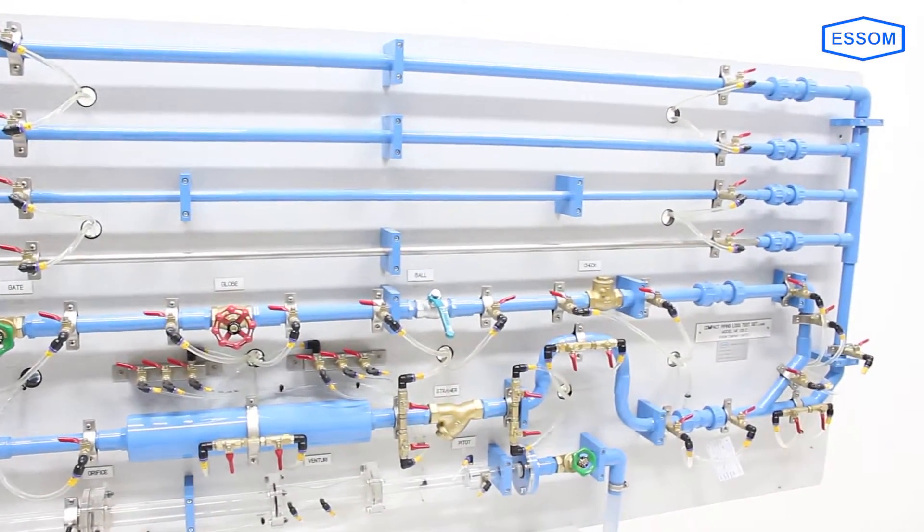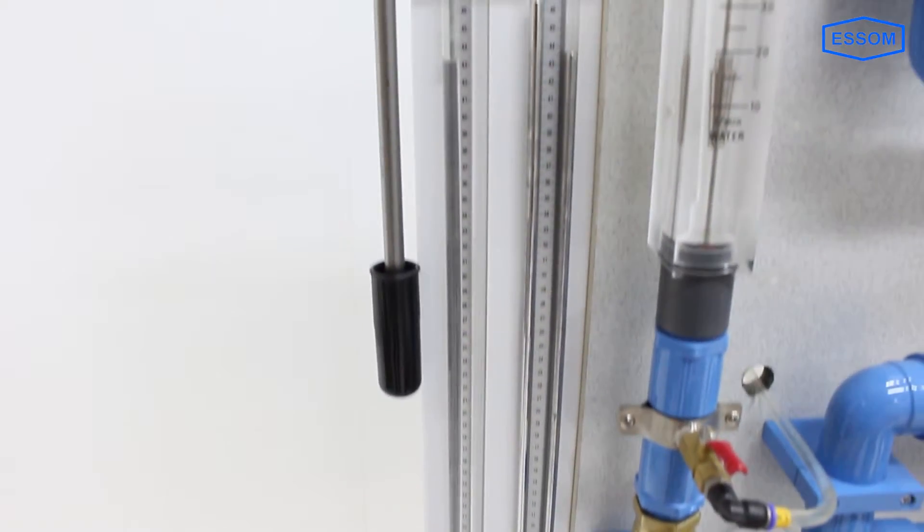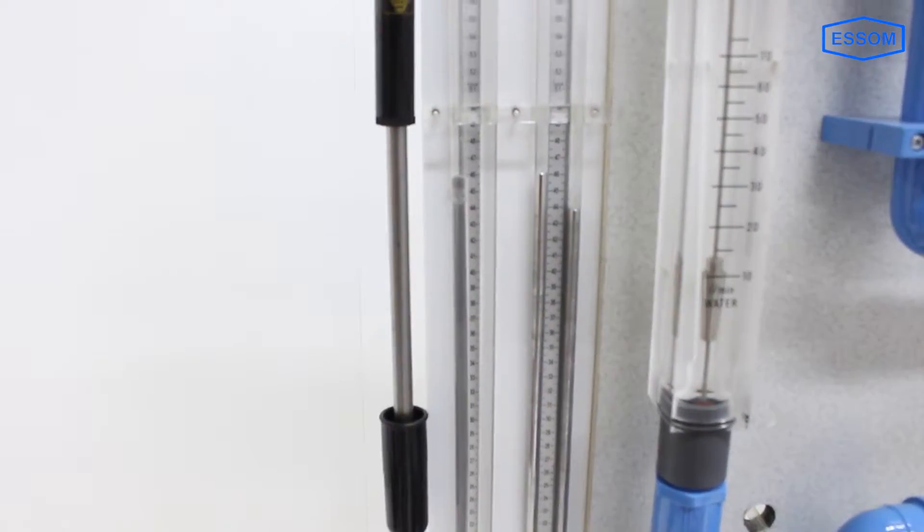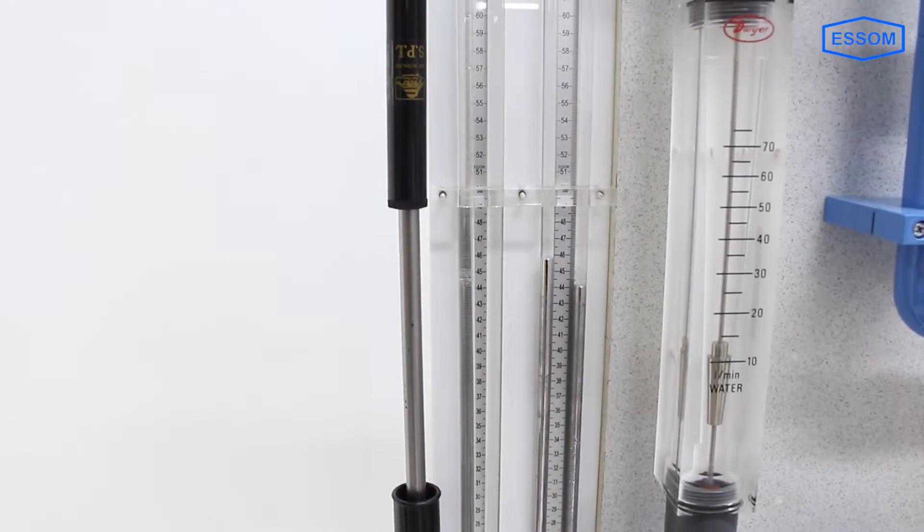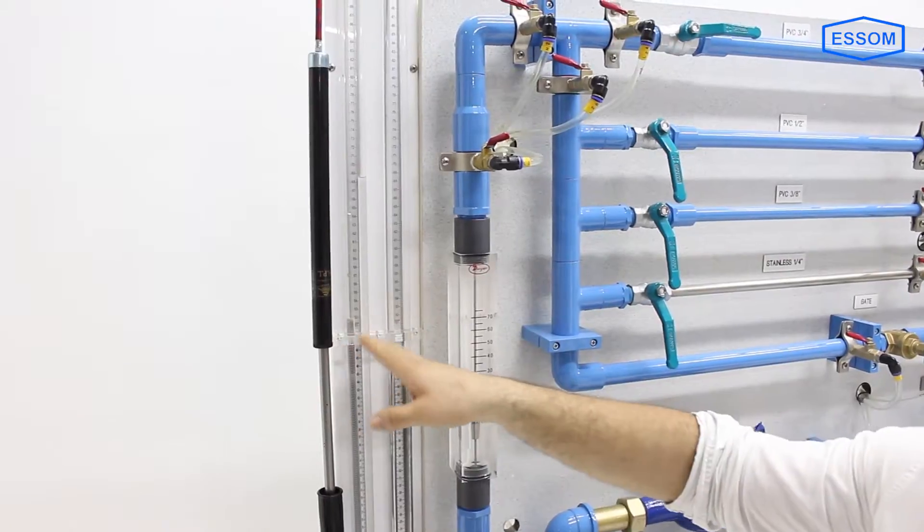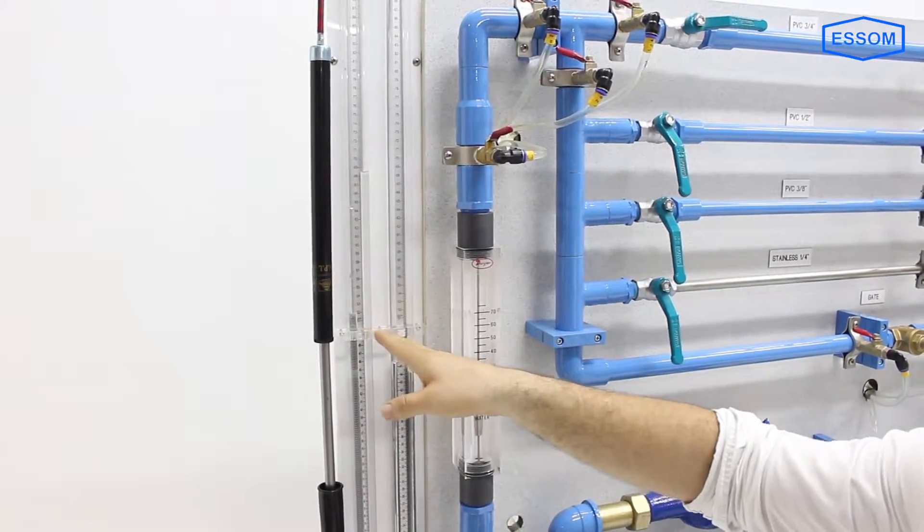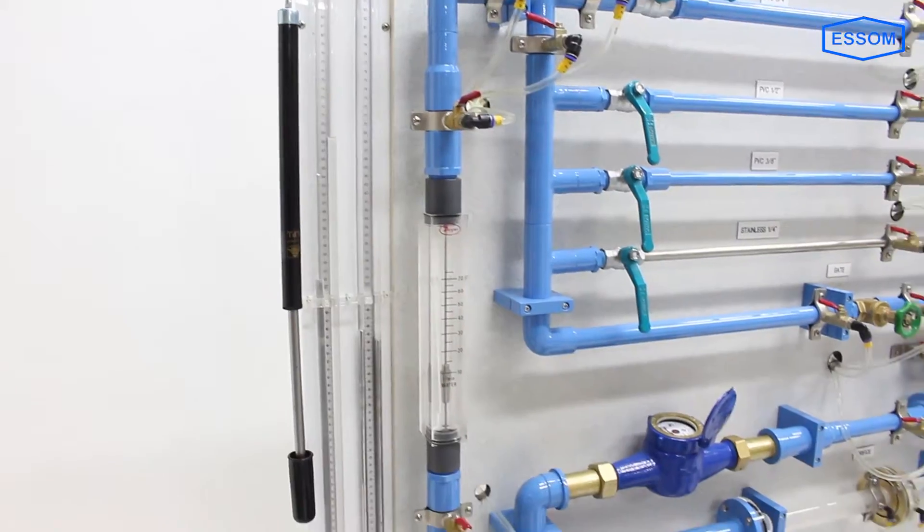The friction loss and coefficient of discharge are measured by differential pressure drop using manometers or a differential pressure gauge as optional.